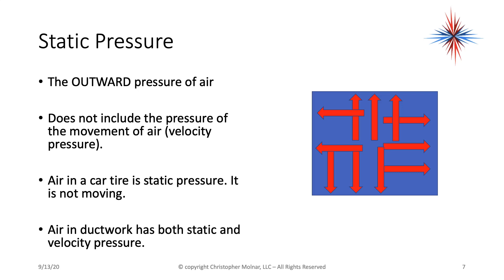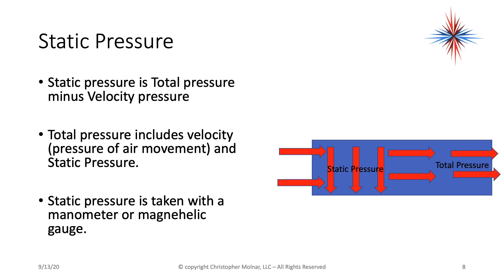You're going to hear me refer to static pressure, so let's quickly define it. Static pressure is the outward pressure of air — air pressing out on any object at right angles to the surface. It does not include the pressure of the movement of the air, which is velocity pressure. Air in a car tire is static pressure — it's not moving and has no velocity. Air in ductwork, because it's moving, has both static and velocity pressure.